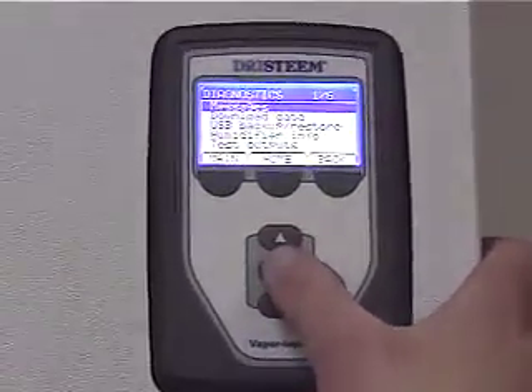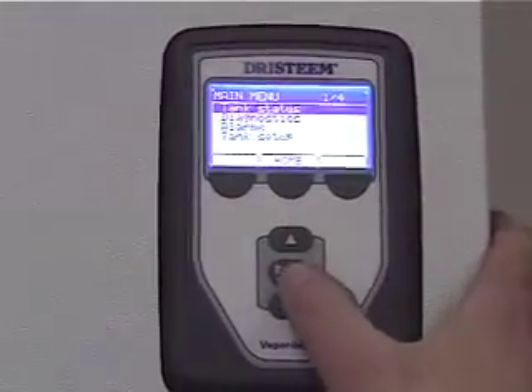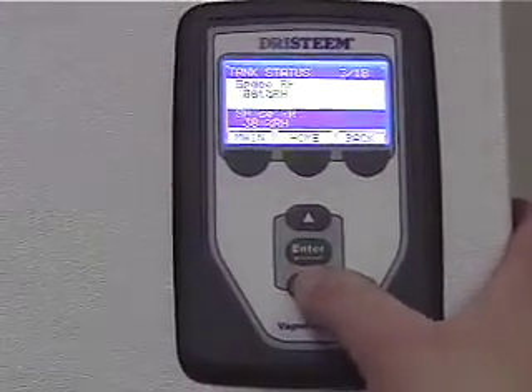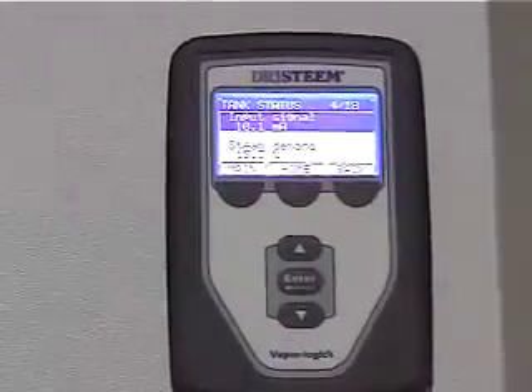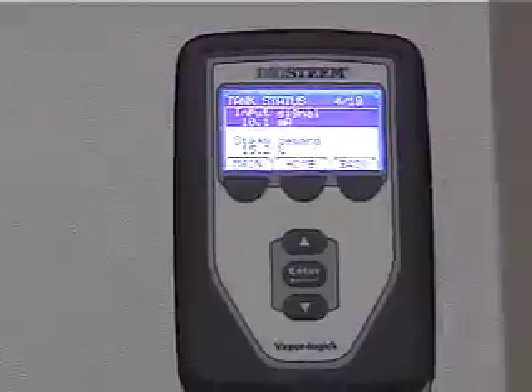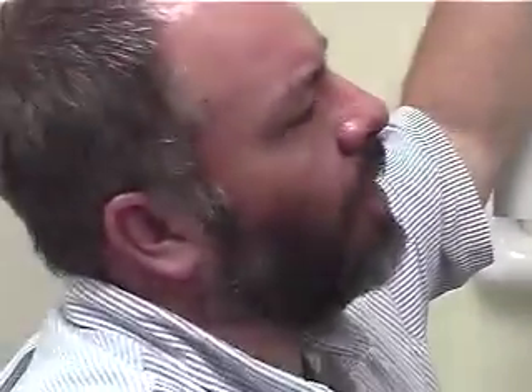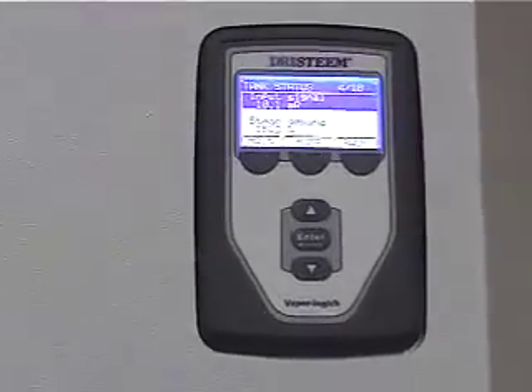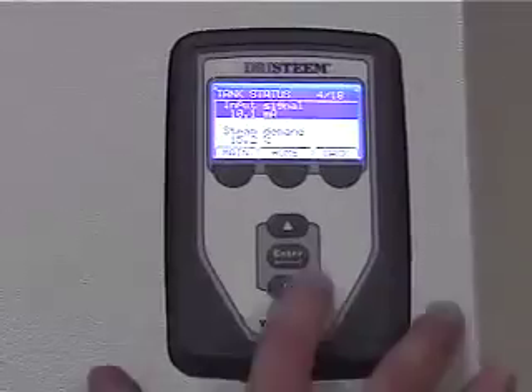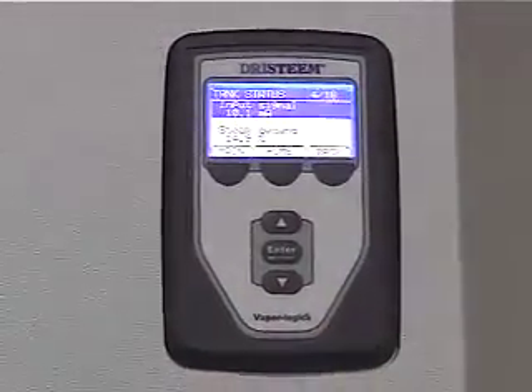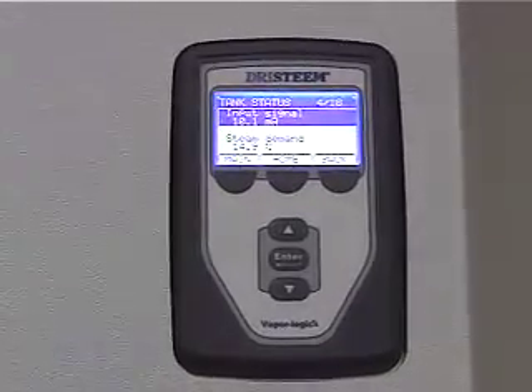So now we can go back in here. Remember, we get back in here to the diagnostics. Tank status. Input signal. We can still see the input signal actually hasn't changed yet. The steam demand is now down to 15% instead of 45%. So if you want to get into here, you can actually get in here and watch this. And that's where I was saying, you can watch your signal going up and down, up and down.